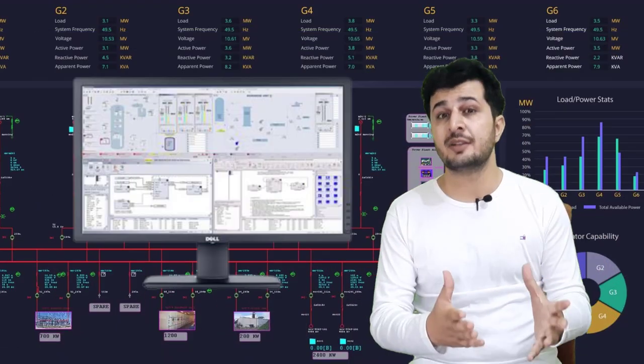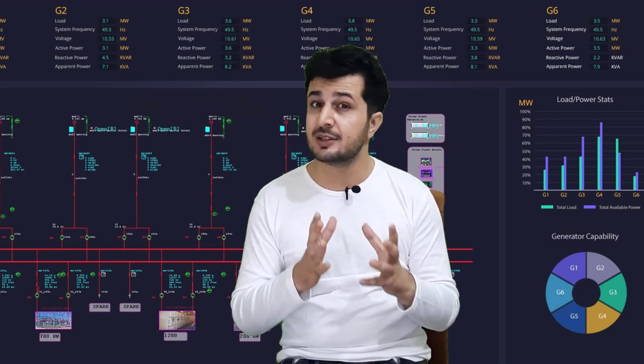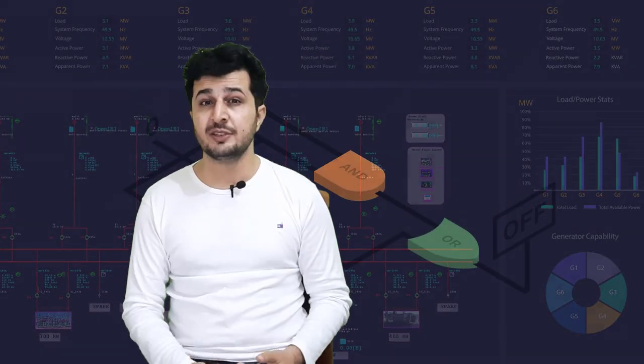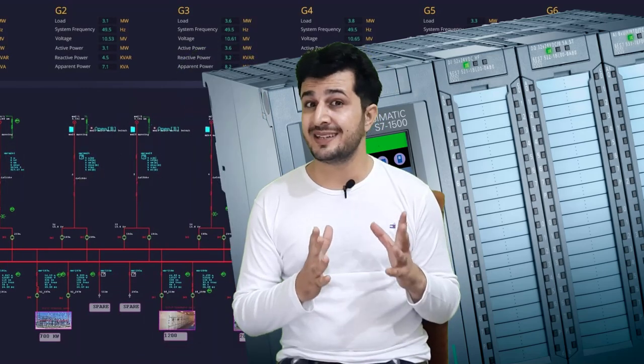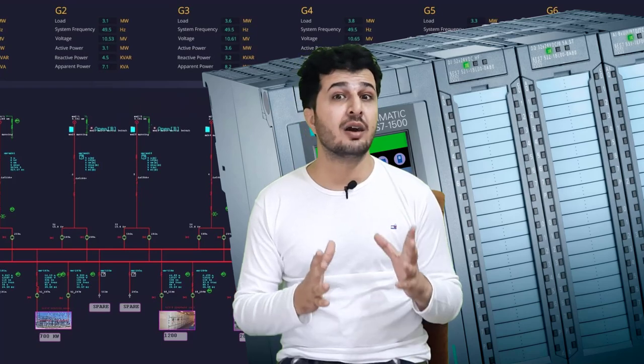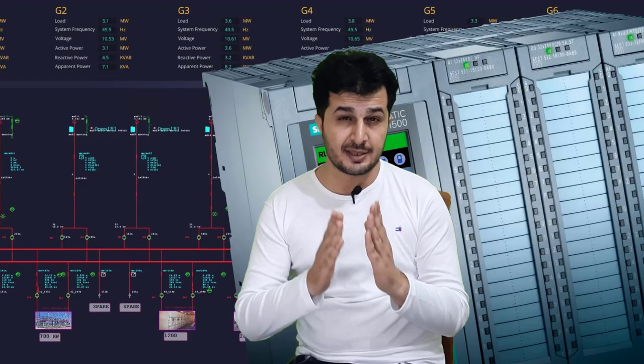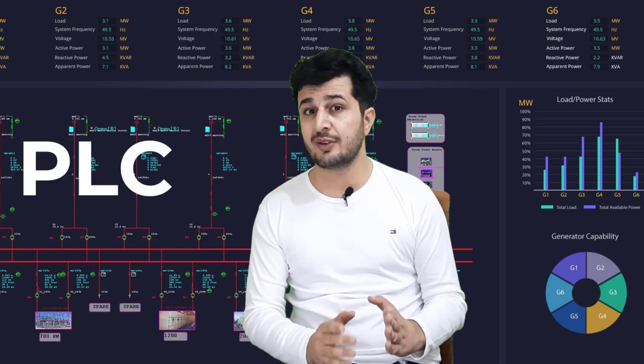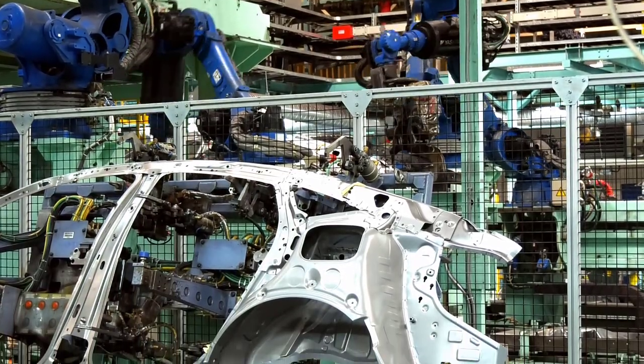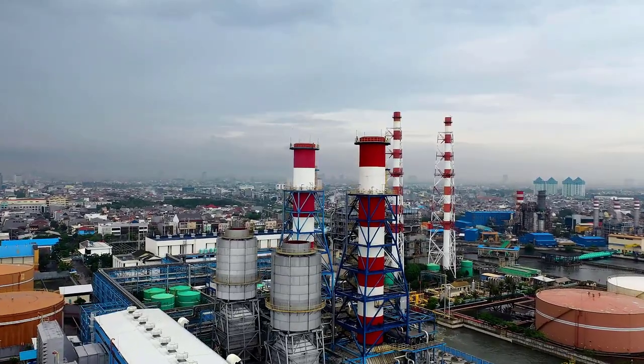If we need to control a single process with a lot of discrete I/Os, then the preferable choice is a PLC. It can also be used when your industrial plant has extensive interlocking. PLC has a faster scan time compared to DCS, which is why it is best for safety interlocks. It has good processing power and is best for manufacturing plants where you have a lot of discrete I/Os.